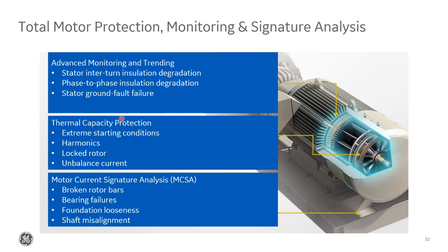So the point here is that traditional motor protection relays are reactive. The elements in the middle section here operate in response to a problem that has already largely happened. Some relays do have more advanced elements that can detect things like winding turn faults, but it still leaves gaps that we aren't covering.